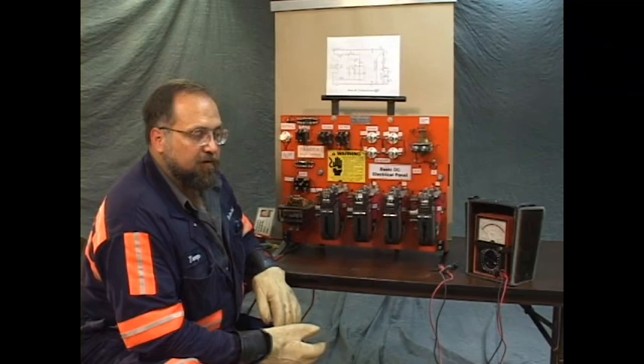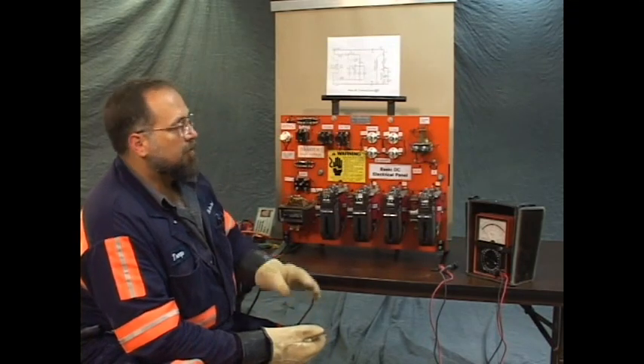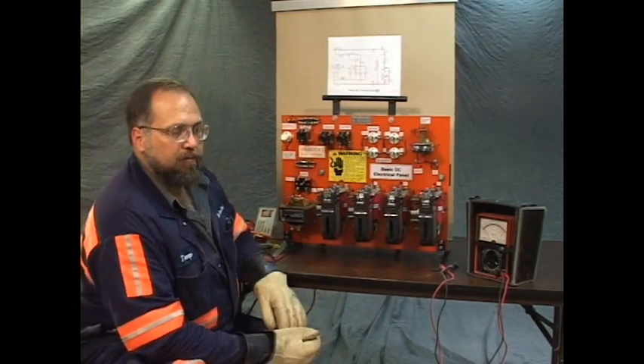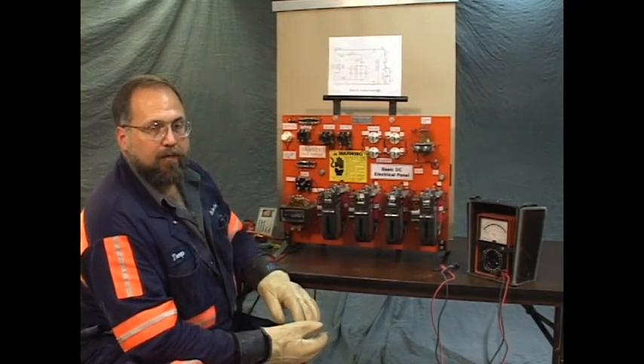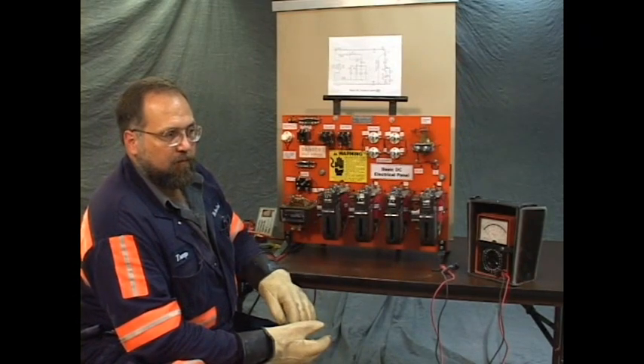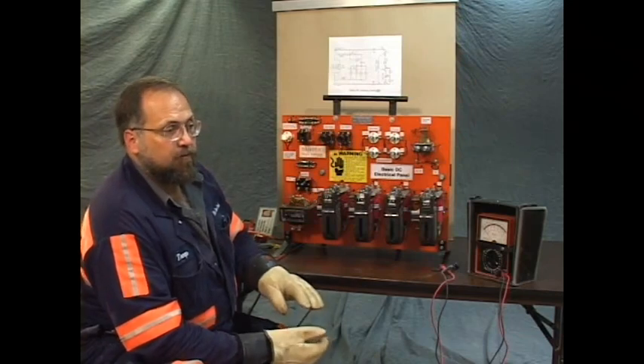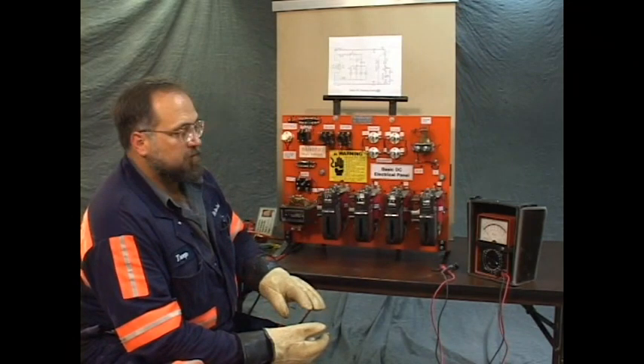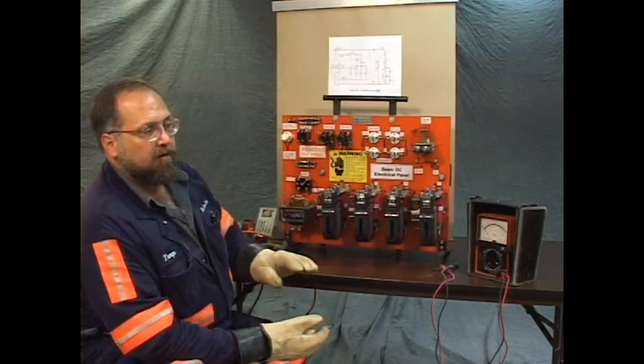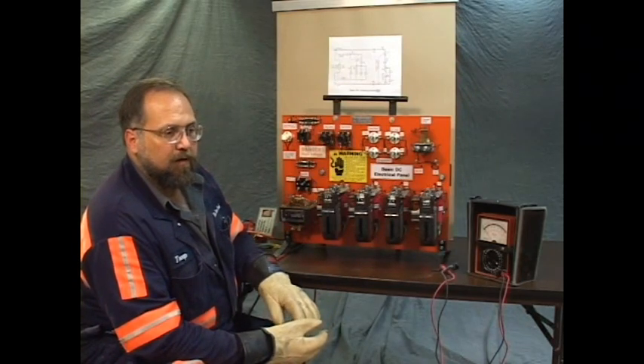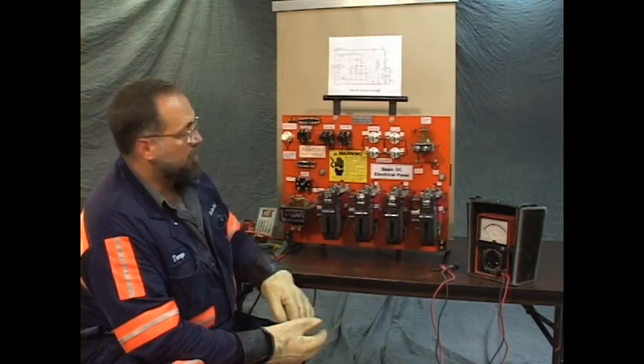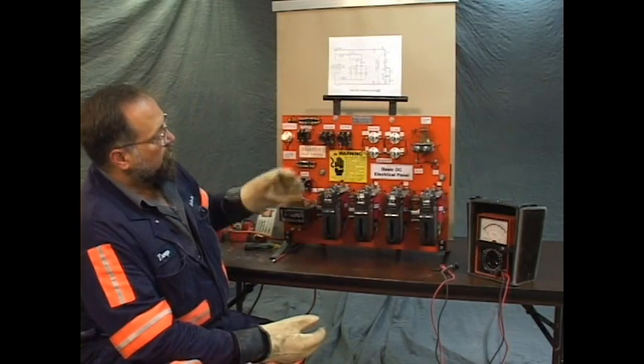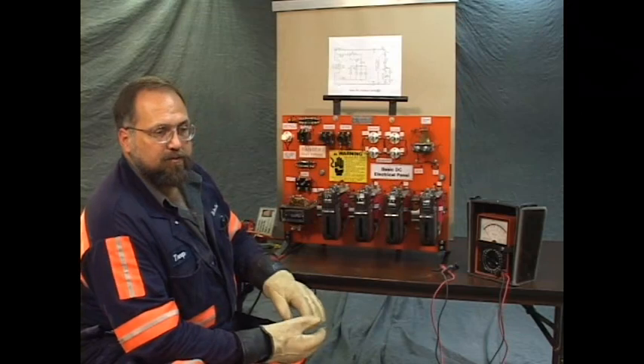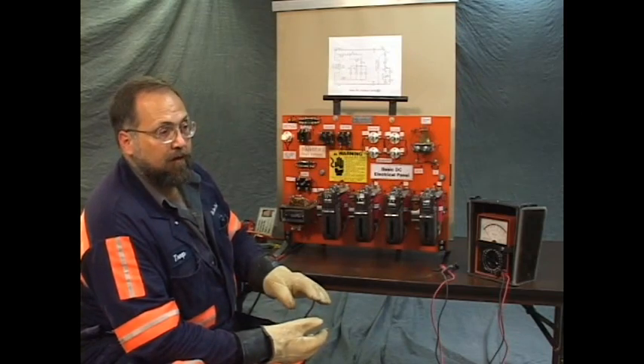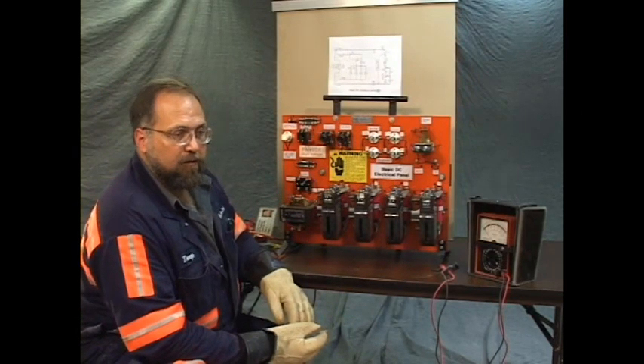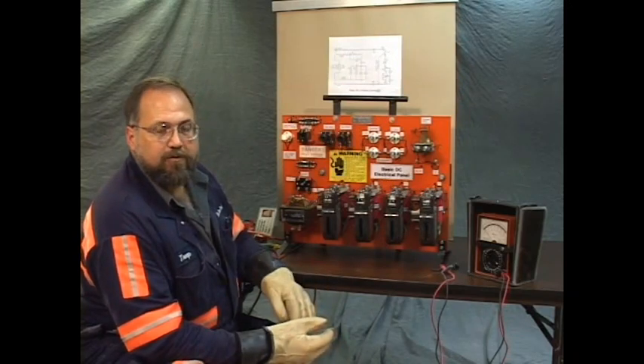Now this is a problem that could exist in real life on a real motor. You could have a shunt field open, not operating, and the motor would still run. You would not have speed control though. A shunt field in a compound motor causes the motor to operate at a certain RPM and be reasonably stable at that speed. Without the shunt field, this would be a regular series motor, and a series motor doesn't offer good speed control. And as a matter of fact, without a load, a series motor will accelerate to the point of destruction. It'll throw itself apart.